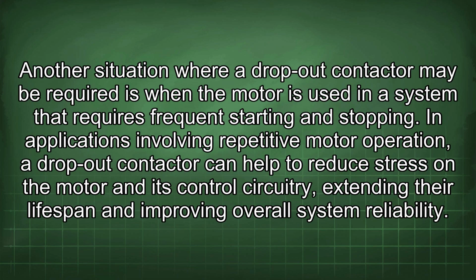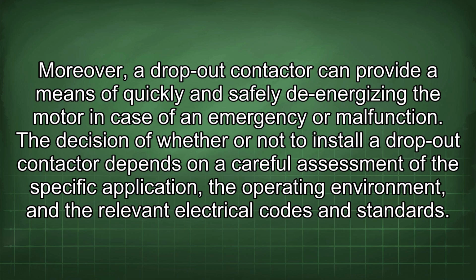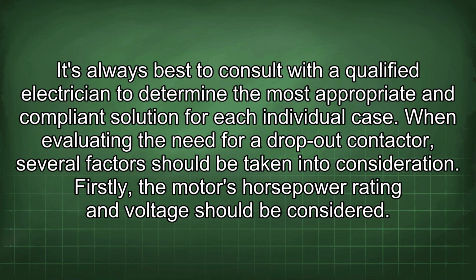Another situation where a dropout contactor may be required is when the motor is used in a system that requires frequent starting and stopping. In applications involving repetitive motor operation, a dropout contactor can help to reduce stress on the motor and its control circuitry, extending the lifespan and improving overall system reliability. Moreover, a dropout contactor can provide a means of quickly and safely de-energizing the motor in case of an emergency or malfunction. The decision of whether or not to install a dropout contactor depends on a careful assessment of the specific application, the operating environment, and the relevant electrical codes and standards. It's always best to consult with a qualified electrician to determine the most appropriate and compliant solution for each individual case.